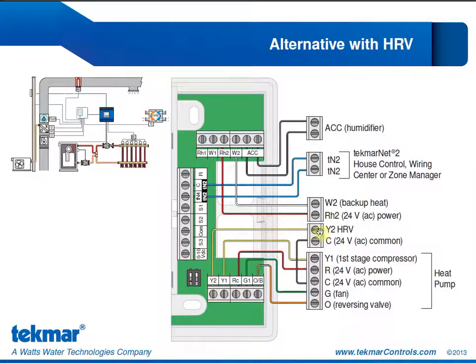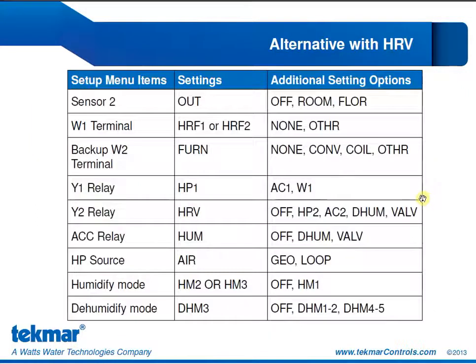Now let's look at our HRV. We have R coming in from the heat pump because Y2 is not an isolated relay. It's connected to that R from the heat pump. Y2 goes over to the HRV, and to complete that circuit, the common has to tie back to the common on the heat pump. Our third stage of heat, the backup electric strip, is an isolated relay, so it's a simple connection, RH2, W2.